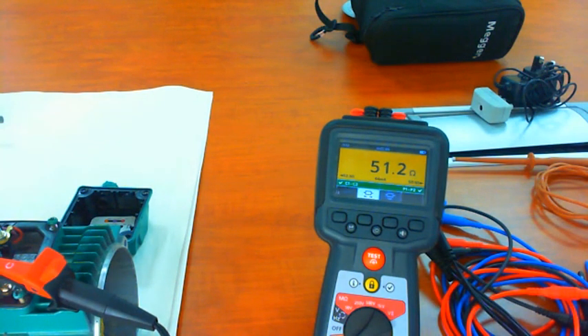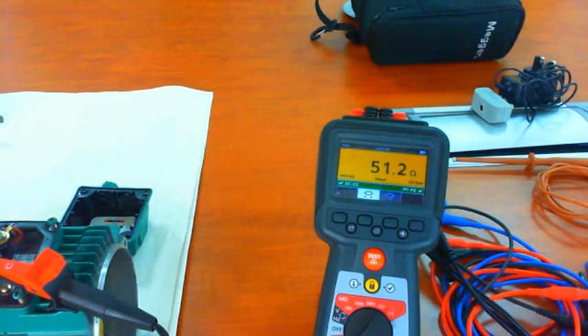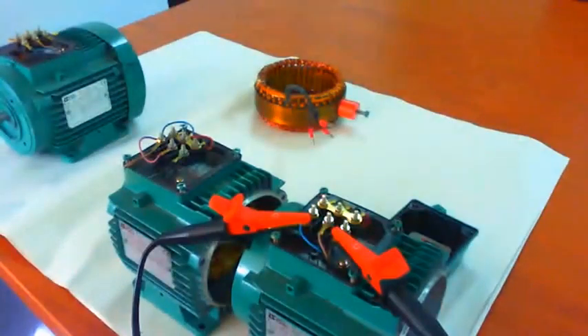So if we calculate the unbalance between those three phases, we take the maximum value less the minimum divided by the average times 100%. That gives us an unbalance of just over 5%. And that's because these stators are two-pole, and two-pole windings are not symmetrical. So we have an unbalanced winding or resistance. But that's a brand new motor. That's a good winding. We can also test our second motor.